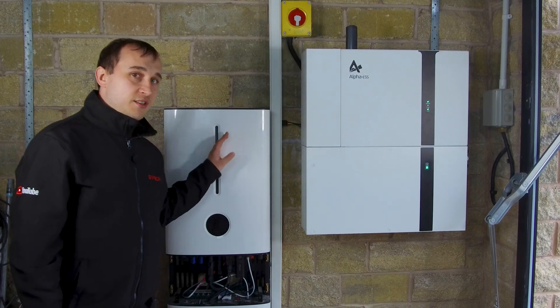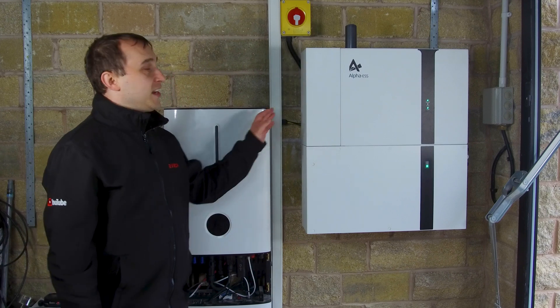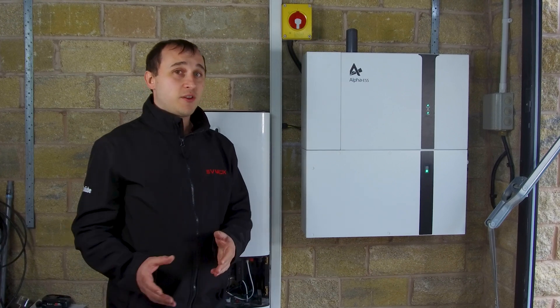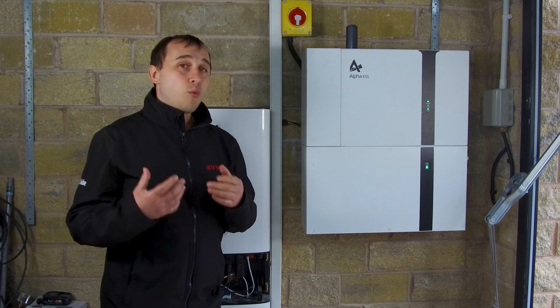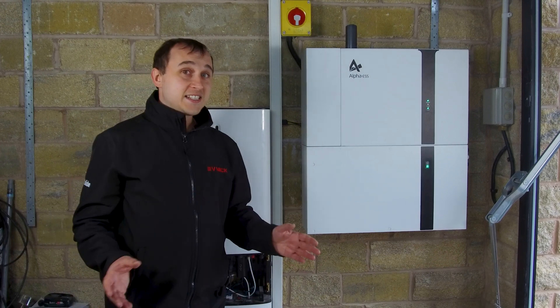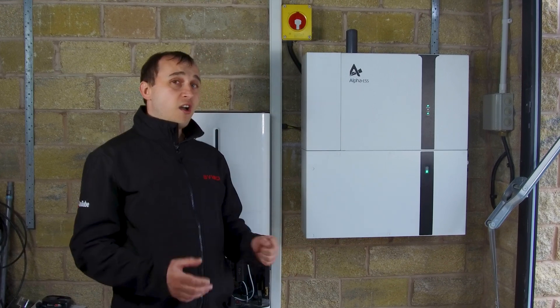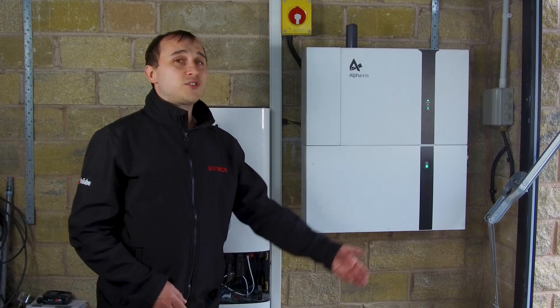The speed at which you can charge your battery is defined by the inverter — the top section of these batteries. Batteries are rated in kilowatt hours (storage), while inverters are rated in kilowatts (charge/discharge speed). Typically you'll see 3.65 kilowatts, but there are also 5 and 10 kilowatt inverters. This matters when sizing — you don't want 40 kilowatt hours of batteries only to find your inverter charges at 3.65 kilowatts. Also, some hybrid inverters can deliver 3.65 kilowatts to your house and charge from solar simultaneously, but cannot charge the battery at the full 3.65 kilowatts, so always check both charge and discharge speeds.